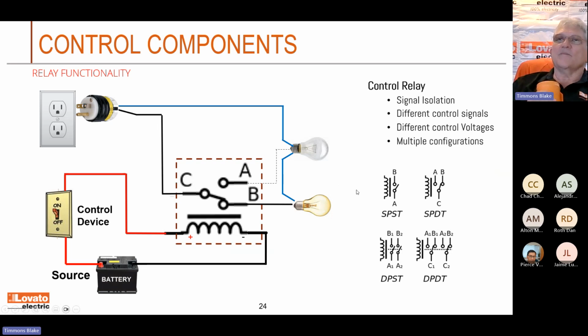Look at this here at the bottom. This is some terminology you need to understand when you're dealing with relays. Let's start off with the first one. That's a single pole, single throw. You see the difference in the single pole double throw, okay? So the poles are definitely the commons, and the throws are the set of contacts. So you can see here at the bottom, I have a double pole. I have two different commons. And then I have a double throw, so it can go either direction. That's some terminology that it's good to be aware of.